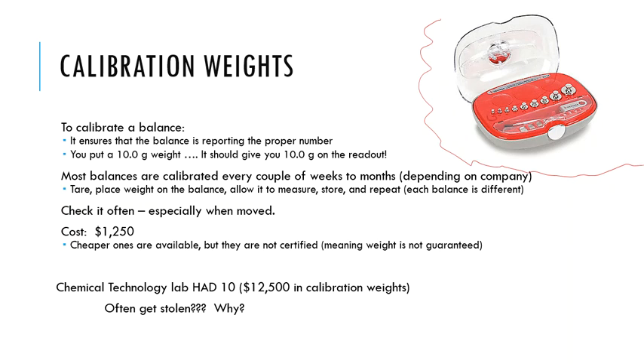So, for instance, what if this little bitty one right here to the left weighs 1 gram? I would take that 1 gram calibration weight, I would put it onto the balance, and I would wait for a few seconds, and I would look at my display. Hopefully there's no drift on the analytical balance, and that number should be very close, if not exactly, 1.0000 grams. That's the purpose of a calibration weight set.